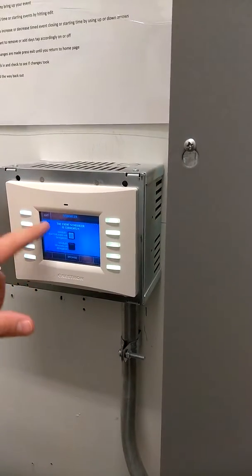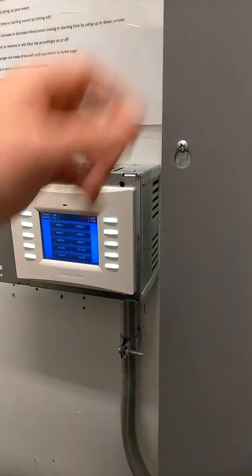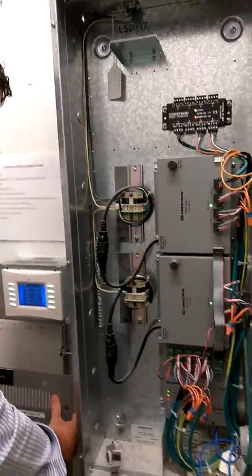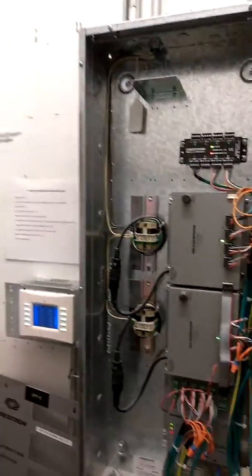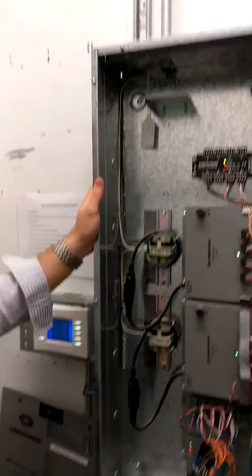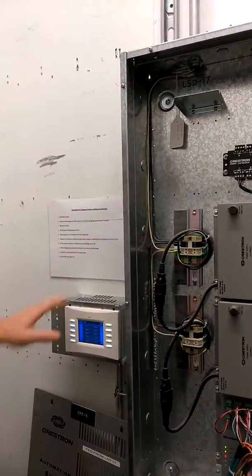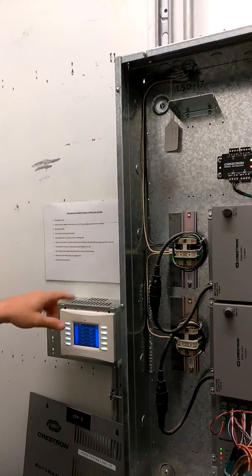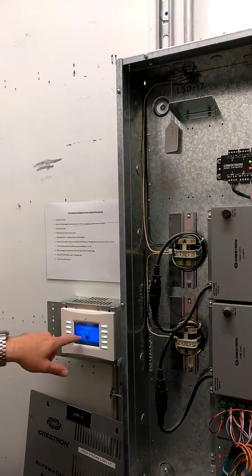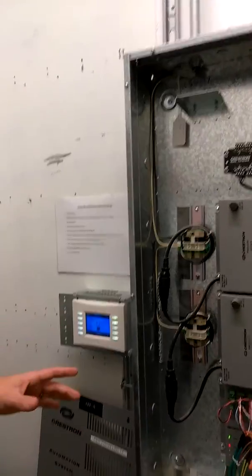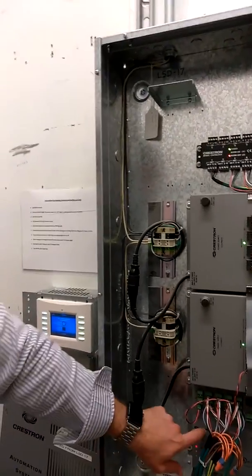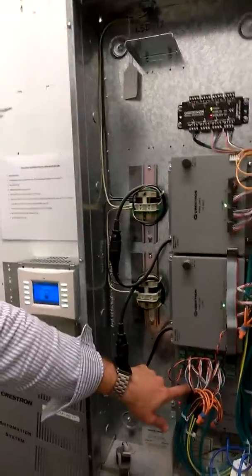So I'll hit exit. And while you're filming, we can go over this quickly. Every floor, floors 2 through 8, has a lighting control cabinet, and they also have touch panels. It's important to note that the scheduled events that I showed you only happen on the touch panel here and the touch panel here on the 5th floor, because the schedule is actually running inside the 5th floor's processor.